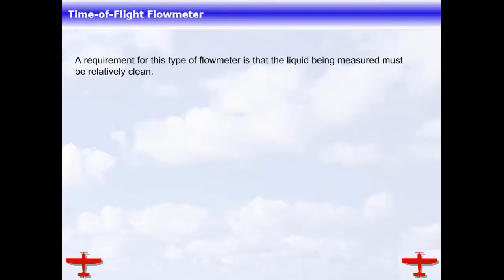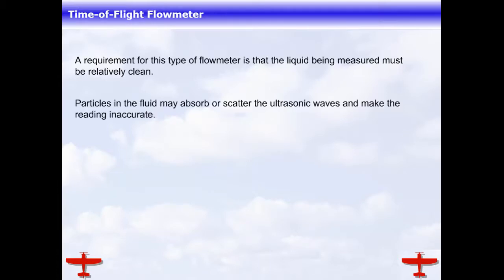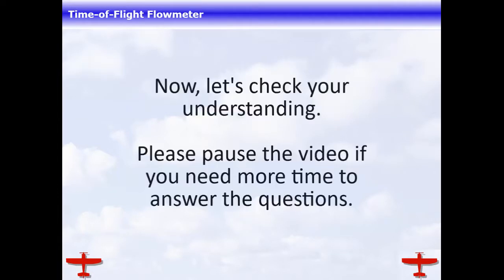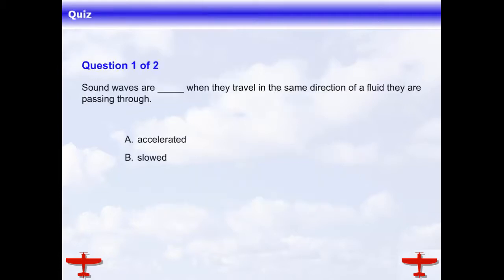A requirement for this type of flow meter is that the liquid being measured must be relatively clean. Particles in the fluid may absorb or scatter the ultrasonic waves and make the reading inaccurate. Now, let's check your understanding. Please pause the video if you need more time to answer the questions.